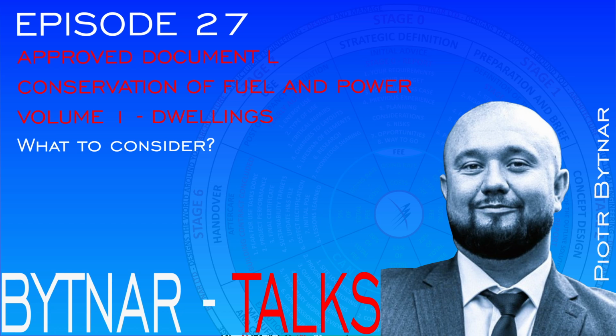Point 1. This regulation applies to building work in respect of a building in relation to which paragraph L2 of Schedule 1 imposes a requirement, but does not apply to the provision or extension of any system for on-site electricity generation where testing and adjustment is not possible. Point 2. Where this regulation applies, the person carrying out the work must, for the purpose of ensuring compliance with paragraph L2 of Schedule 1, give to the local authority a notice confirming that the system for on-site electricity generation has been commissioned.